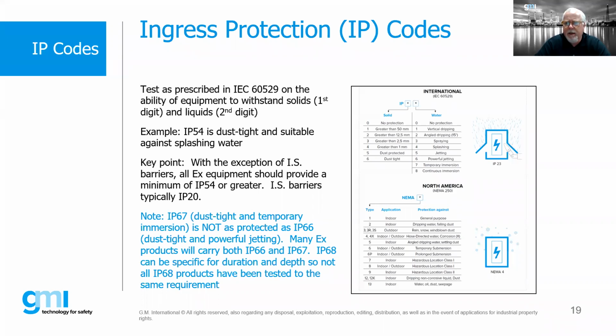Now, generally speaking, a higher IP code will always be suitable for a lower IP requirement. So if I have a piece of equipment that's IP65, it would be suitable for applications where I require IP54. So just like Roman numeral 2C gases is good for all gases, the same thing holds true in this case about high IP ratings. Oh, one last thing on this.